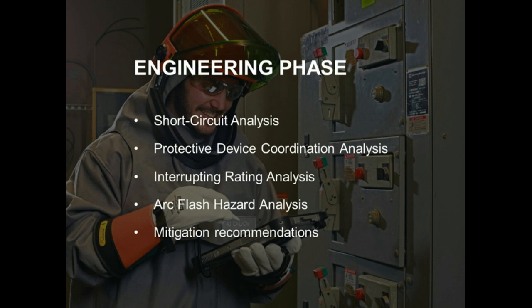But we have to have all of this done in order to provide mitigation. So if you're talking to someone, or getting ready to do this on your own, make sure you're doing everything listed here - all 4 of those assessments, all 4 of those analyses, in order to properly mitigate the hazard. You have to know everything about why an arc is higher in one area than another in order to fix it. This is a very important part of your arc flash assessment, your incident energy analysis - making sure you're doing the right studies to get to the common goal, which is getting rid of these hazards.